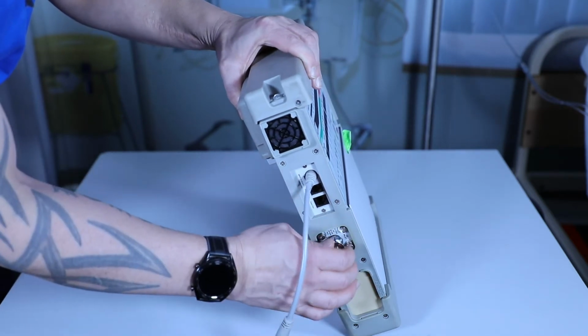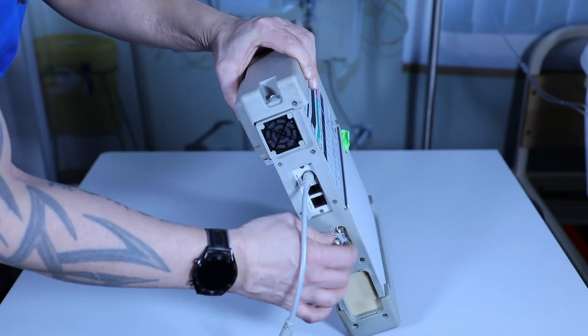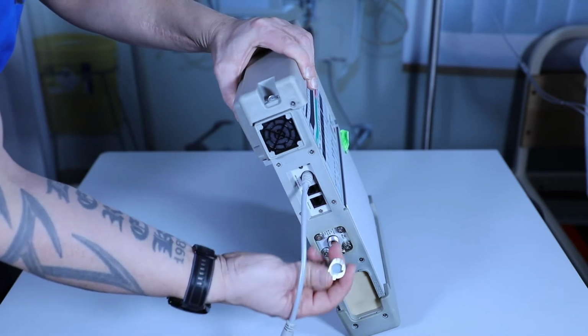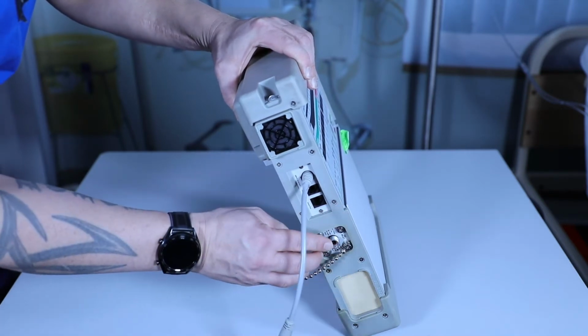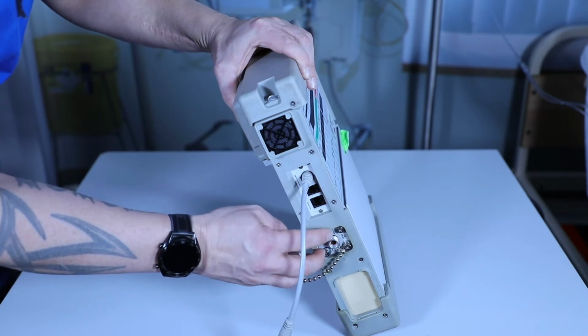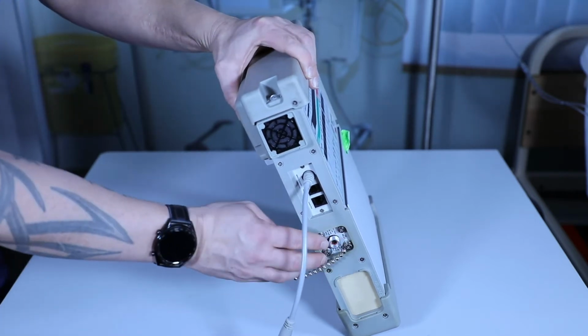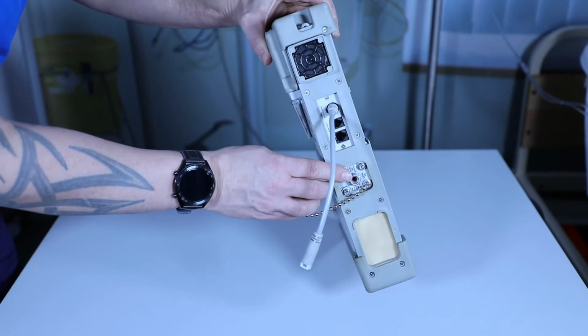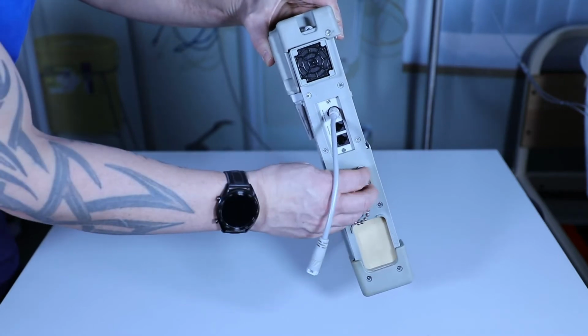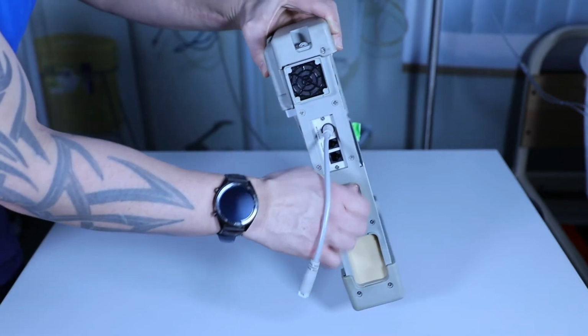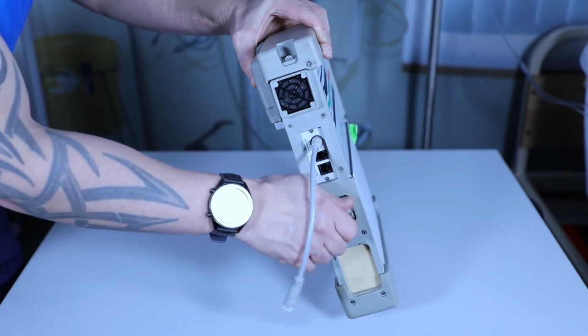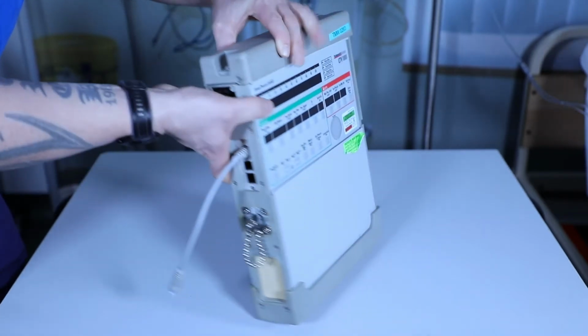The next thing we're going to inspect is the O2 hose. We need to ensure that the cover is intact with the lanyards. We can then inspect the connection port more closely, ensure there's no damage and that it has a red rubber seal which is present. Once we're happy with that, we can reattach the O2 cover, and that's the physical checks of the machine itself complete.